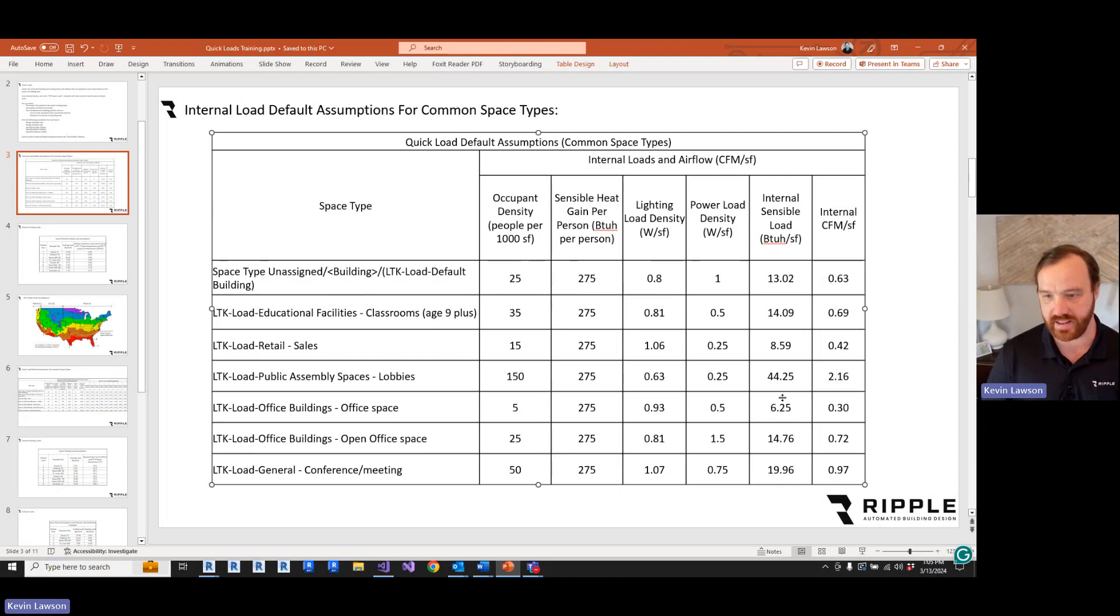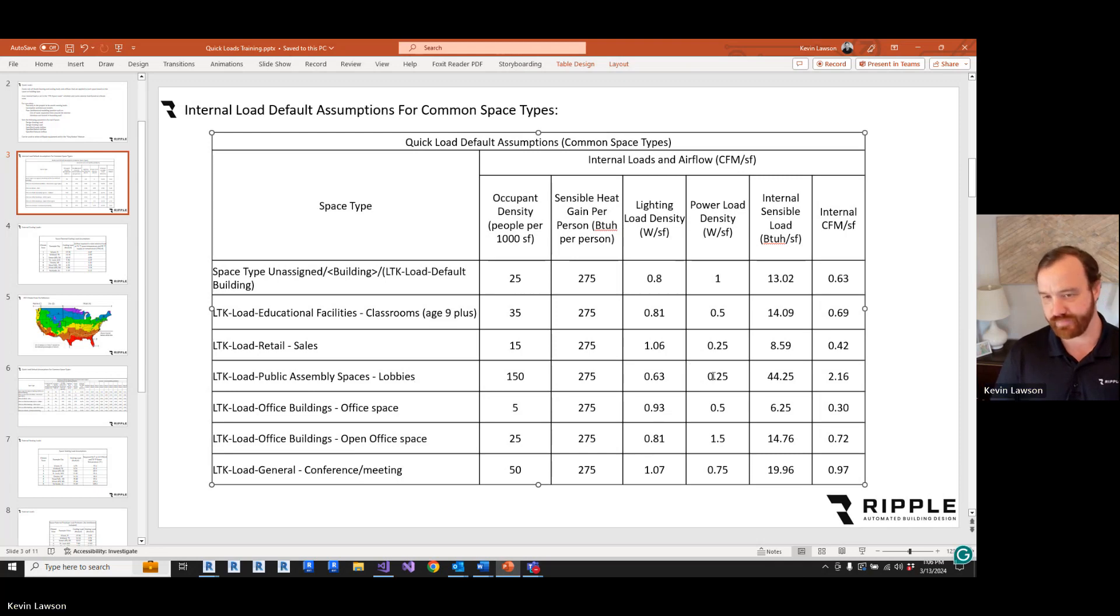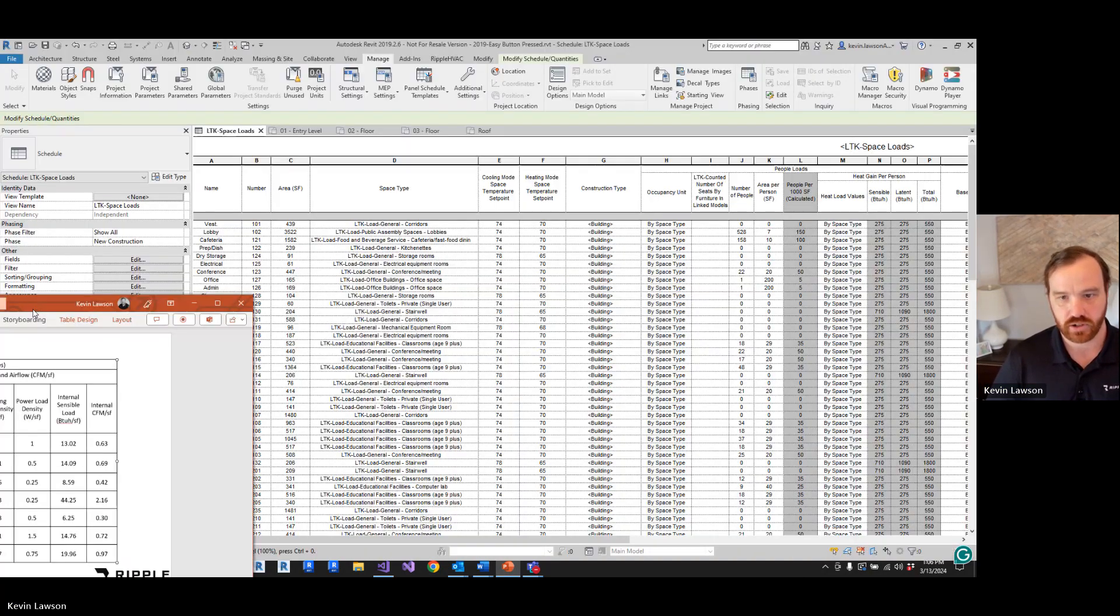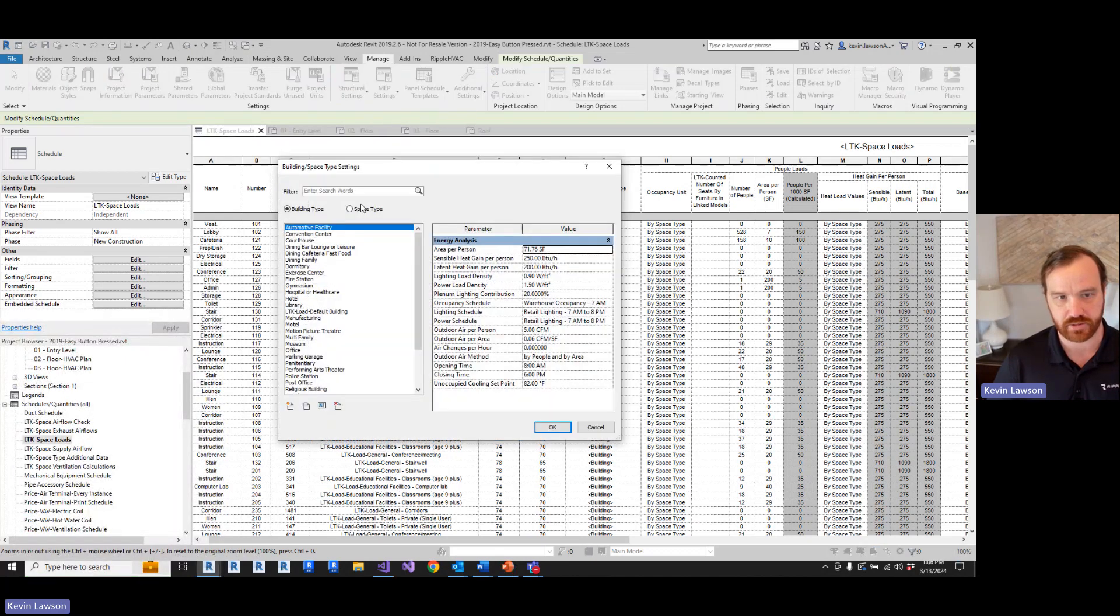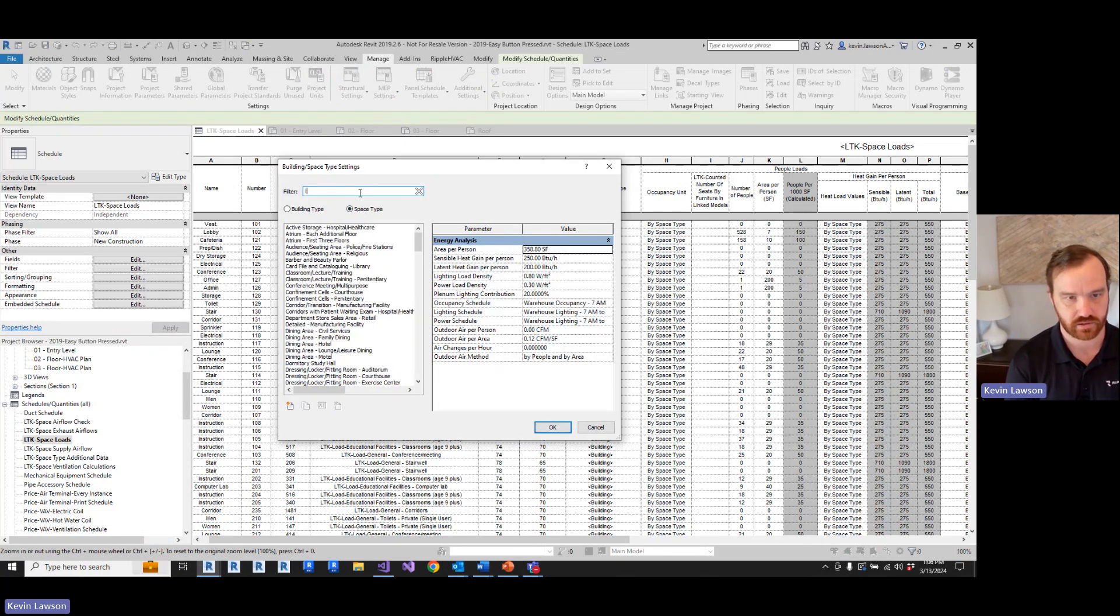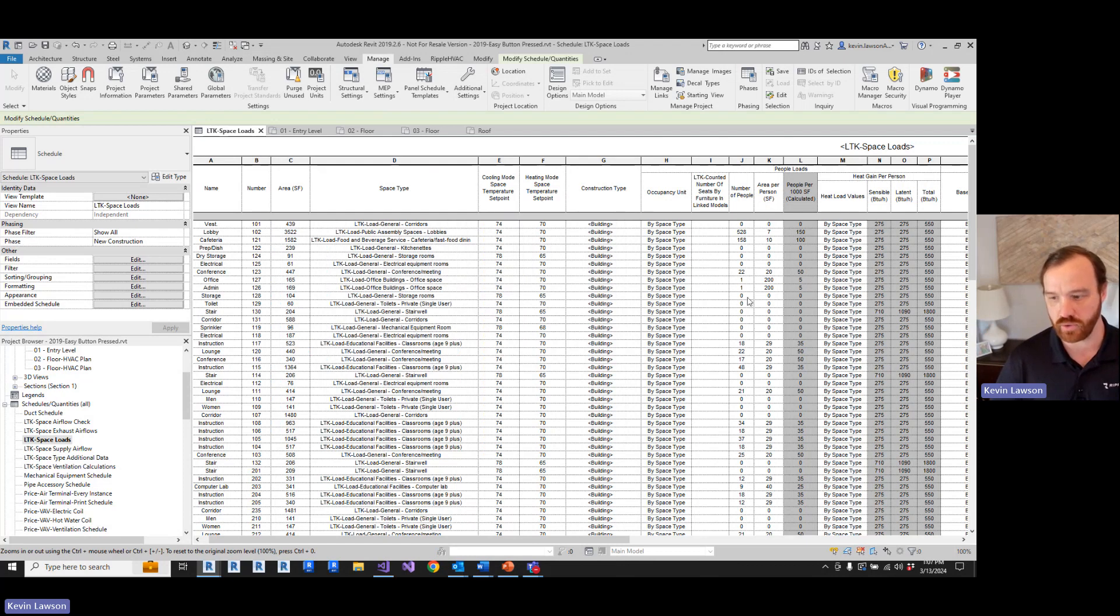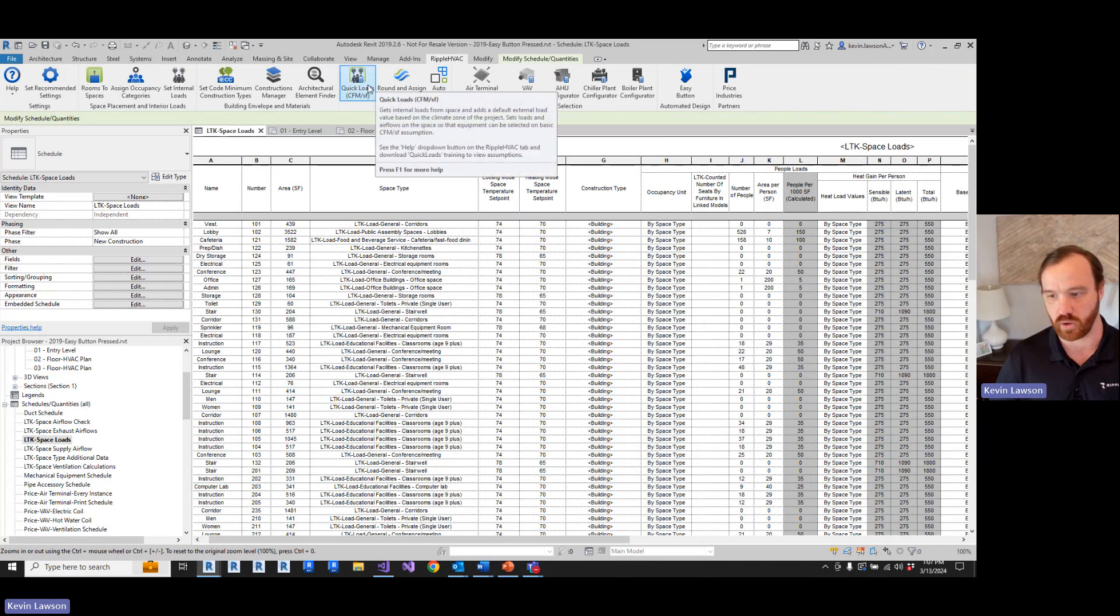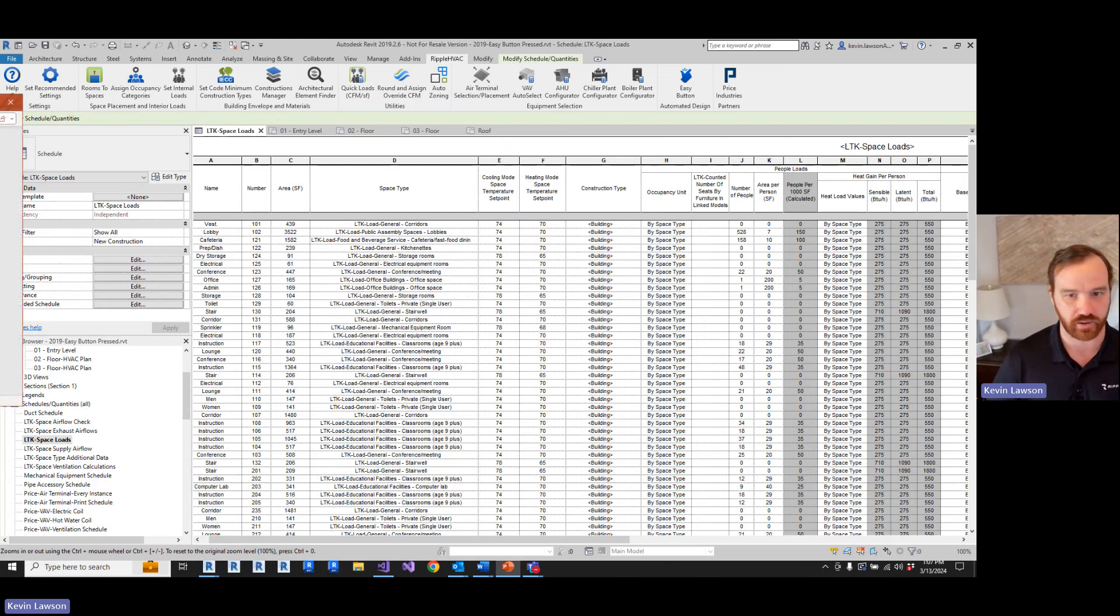Now, if you don't like any of these assumptions, you can change them. I have by default a power load density of 0.25 watts per square foot for lobbies. Now, that may make sense, it may not. Maybe you want to assume there's no power load going on in these lobbies. So if you want to change that, you go to manage, MEP settings, building space type settings, space type, let's look at lobbies. We have public assembly spaces - lobbies, 0.25. You could just change that to 0 watts per square foot. And now your internal load will be changed when you run the quick loads tool. If you change these settings on your template file, now whenever anybody in your company starts a project from that template file, they'll have those default internal loads set correctly.